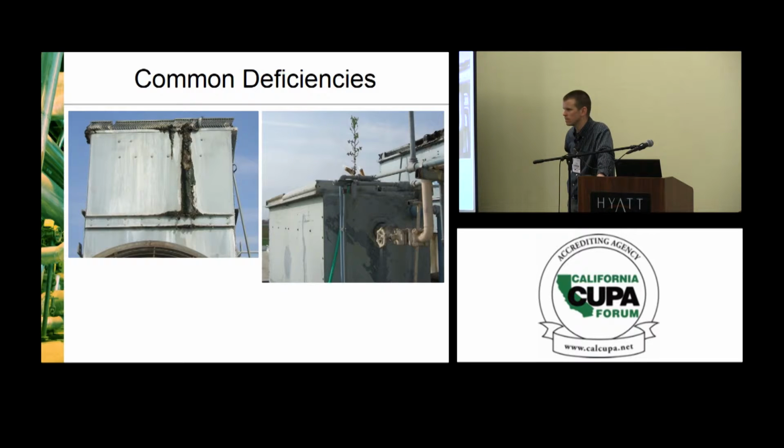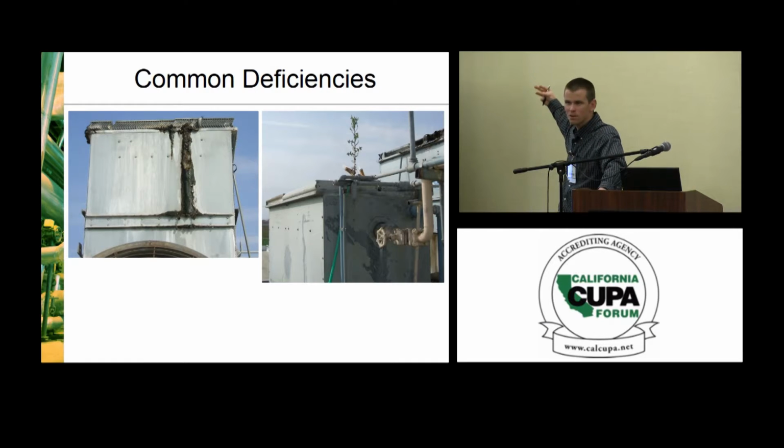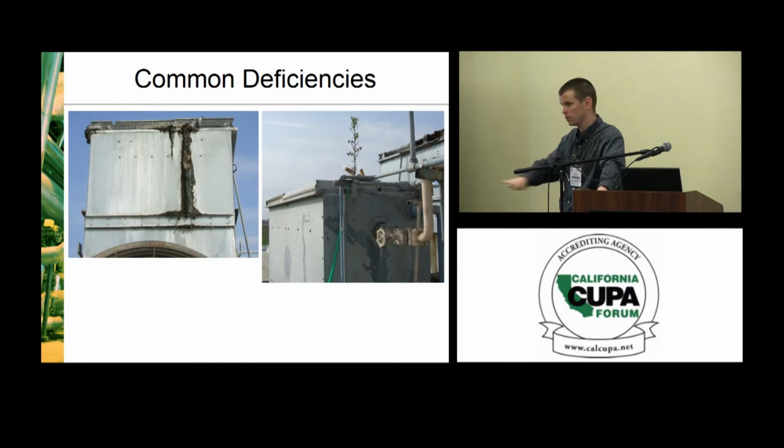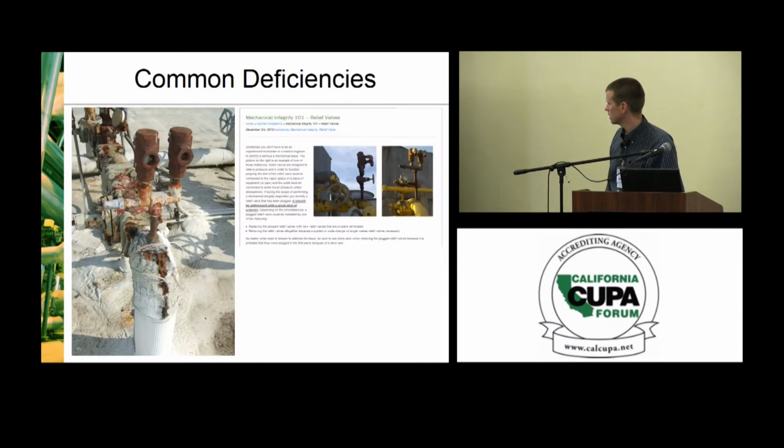If you're in a really dusty, dirty agricultural environment, which a lot of facilities we work with are, the condenser could be renamed an air filter, because it pulls that dirty air through water, which washes all the dirt out, and you get super clean air coming out the top, and then the dirt sits in the bottom, right? And that's why it gets all mucky and dirty. But if you're in an urban environment and it's mostly city, not a ton of dust, the amount of crud that will build up in the bottom will be less. It will be very site specific, is what I'm trying to say. And so operating experience is really valuable when it comes to evap condensers.